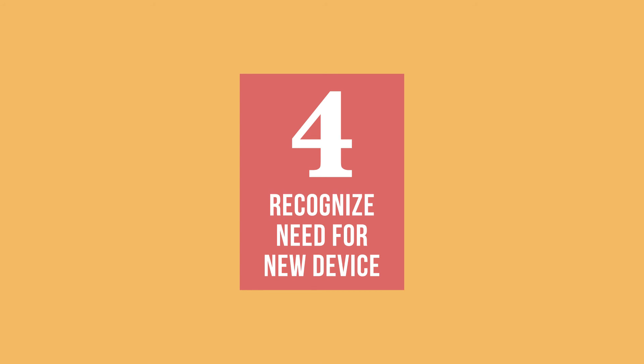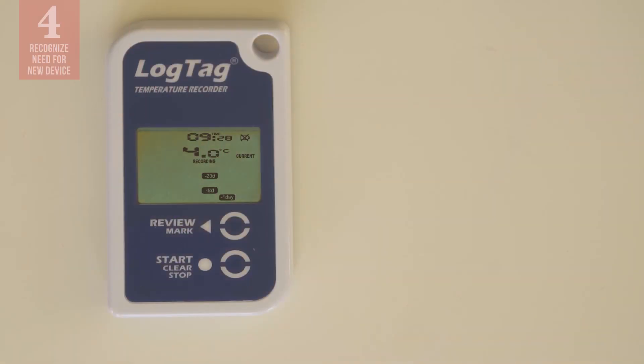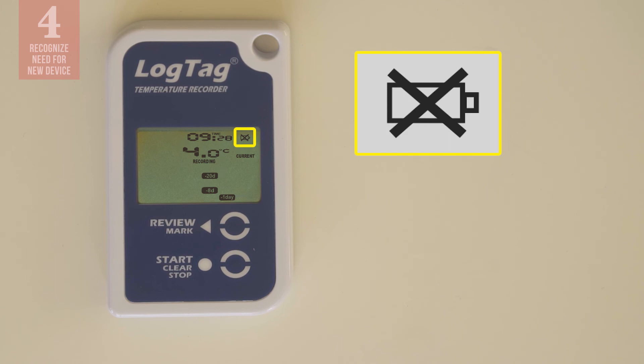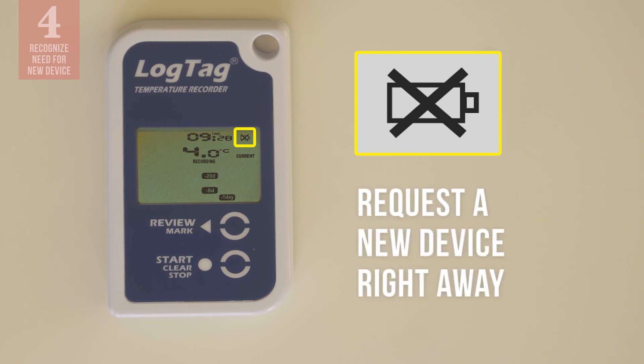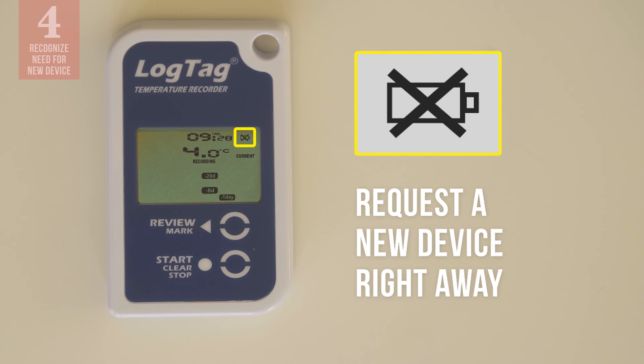Now let us look at the last important task: to recognize when you need a new device. If you see a symbol on the screen of your device that looks like this, it means the battery in your device is running low. That means you need to request a new device right away, since you cannot replace the battery in a LogTag.